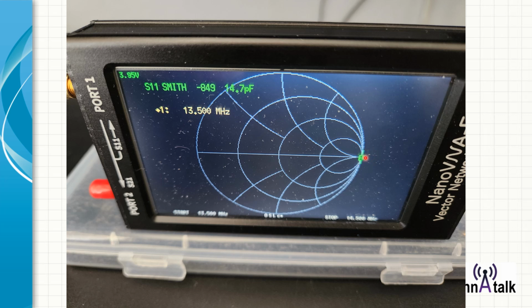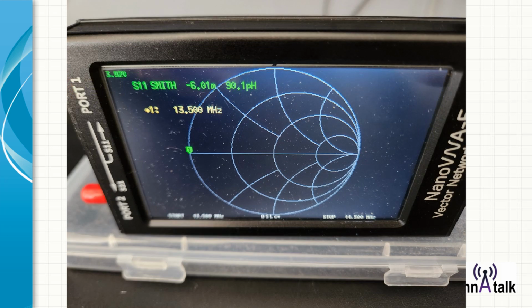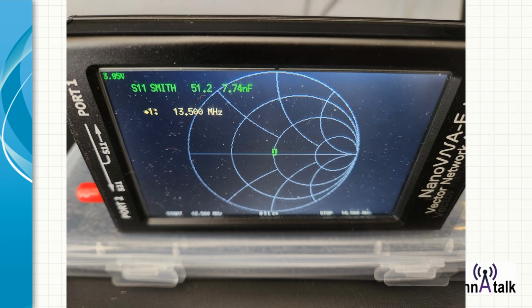Now, we're going to show you three slides after it's all been calibrated, not during calibration, but after calibration. So this is the open, because remember, the center of the Smith chart was 50 ohms. Over here, it goes down in resistance to a short. Up here to the right of 50 ohms, it rapidly and logarithmically goes up in resistance until it's an open. So at the 3 o'clock position, it's an open. We put a short here. We apply a short cap on here, and we should see a perfect short. And when we apply the load, you should see the 50 ohm load dead center. And look, 51.2, close enough for government work.